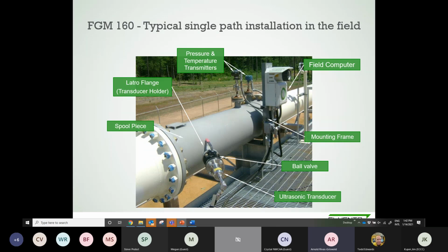We may add a mounting frame to make sure we have that flow computer close to the sensors. We have a certain distance that we can provide for these cables, up to about 30 meters. With that, you can put the field computer in different places. But typically, I think the standard is 10-meter cables. And then we have pressure and temperature measurements. Like I said, those are part of the inputs. The other inputs we receive are from the sensors themselves.